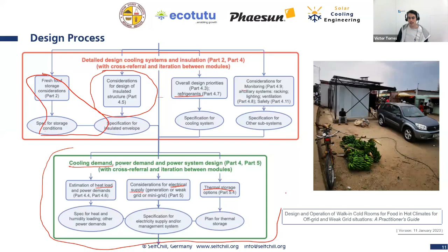So that when somebody needs to have a cold room that needs to store a certain amount of a certain product, we can actually say, okay, the cold room should be like this. It should be run by this amount of PV panels, this amount of cooling units. This is how the system would look like. I have the design and I have a cost for this, because you will discover today the different conditions or specifications modify a lot, or affect a lot, the cost of the system.